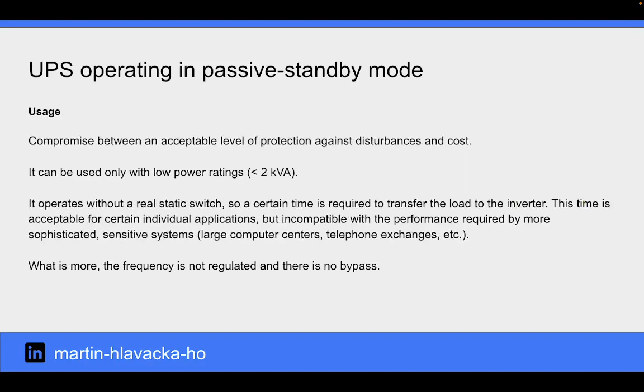This configuration is a compromise between an acceptable level of protection against disturbances and cost. It can be used only with low power ratings. It operates without a real static switch, so a certain time is required to transfer the load to the inverter. This time is acceptable for certain individual applications, but incompatible with the performance required by more sophisticated sensitive systems. Also, the frequency is not regulated and there is no bypass.